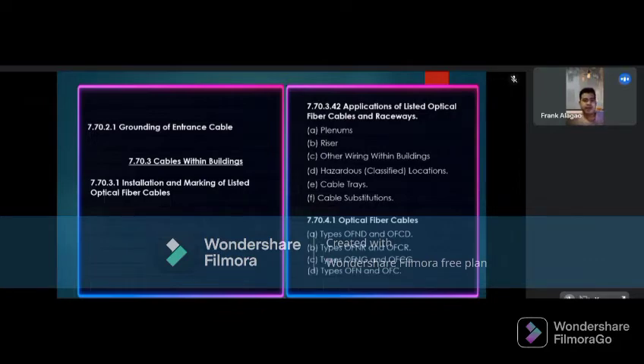So next one is Article 7.70.2.1, grounding of entrance cables. Grounding of entrance cables: where exposed to contact with electric light or power conductors, the non-current-carrying metallic members of optical fiber cable entering buildings shall be grounded as close to the point of entrance as practicable or shall be interrupted as close to the point of entrance as practicable by an insulating joint or equivalent device.